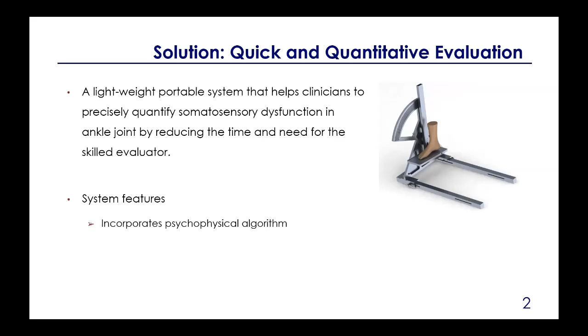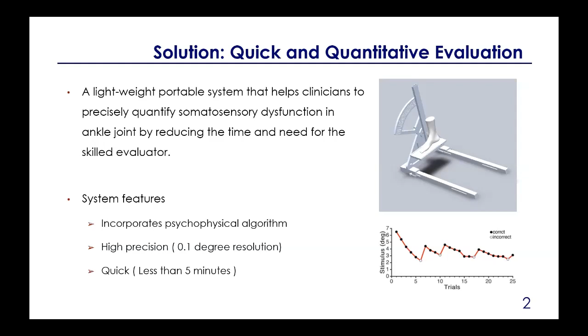The system incorporates psychophysical algorithms to precisely measure the somatosensory threshold of the individual. The evaluator only needs to follow the instructions from the developed application and move the participant's ankle into different positions known as a stimuli value. The precision of the system is 0.1 degree. After 20 trials, which will take up to 5 minutes, the application will calculate the threshold and report it to the evaluator. This way, the need for the skilled evaluator is eliminated. The system is suitable for monitoring longitudinal therapeutic success by eliminating inter-rater variability.